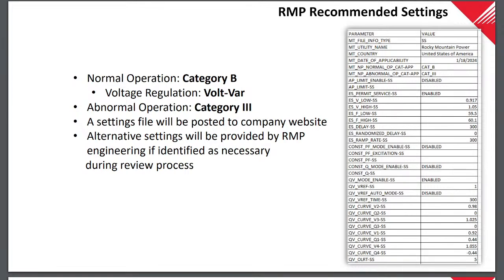There's the volt-watt option, which seems to have a bit better voltage control. From experience — well, I don't have direct experience with volt-watt control, just from reading some studies — it seems like that's the next step in voltage regulation. The problem is that it limits the output of the inverter, so the homeowner or customer might not see the full output. Whereas with volt-var, when you have normal voltage, the vars will be zero, so you still get the full benefit of the watt output, the generation.